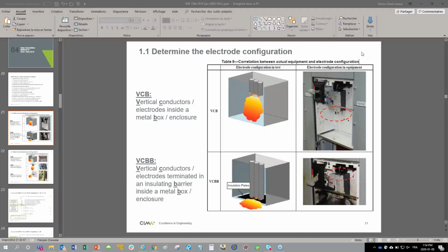I like it. All right, so the next one, which is the method to work or use over 15 kV from the point of view of the standard and from EasyPower? So, in my opinion, if you're just above 15 kV, let's say up to 25 kV, the Lee method is pretty appropriate. There are some other software that can be used for voltage above 15 kV. Or I don't know, Jim, do you have some comment on that from the opinion of EasyPower?